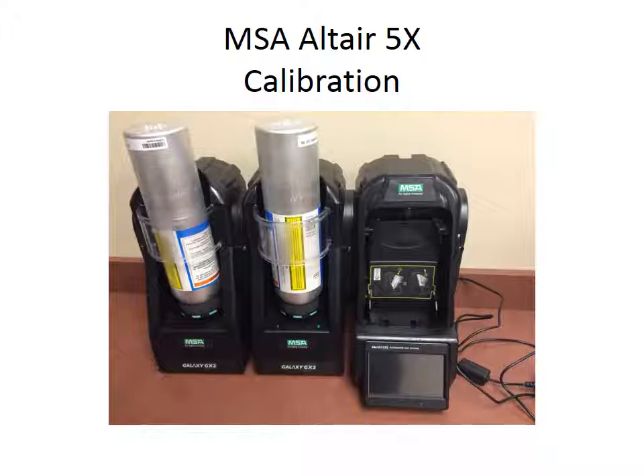But it's very simple to use. It turns on, you plug it in. The little screen on the bottom right of the unit is a touch screen. It displays where you're at. Once you turn it on, you turn the meter on, and then you just plug the meter into the sampling port, the little connection point on the right side of the Galaxy unit. It just pops in there, very simple, and it does the calibration automatically on its own.